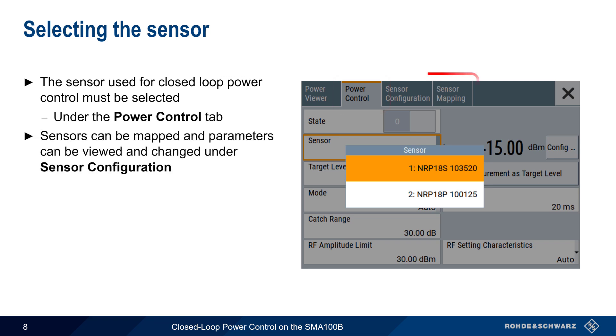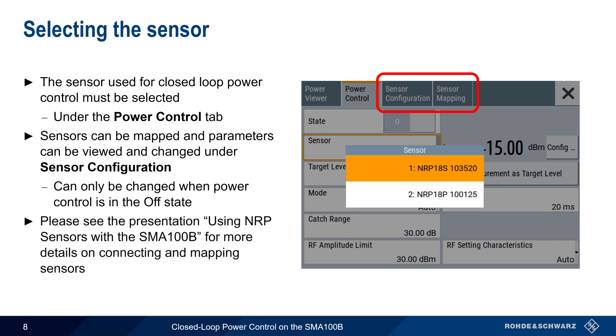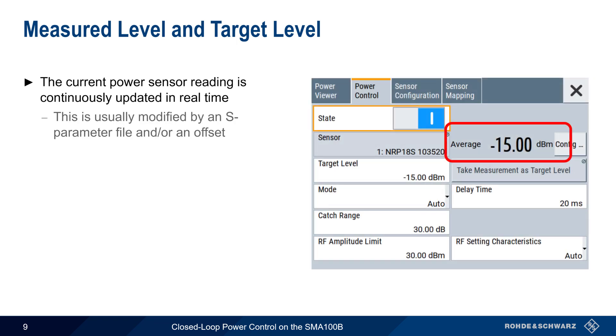Attached sensors can be mapped and parameters can be viewed and changed under the Sensor Configuration and Sensor Mapping tabs. Note that this is only possible when power control is in the off state. In this presentation, we won't go into detail on how to attach and map sensors, so please see the separate presentation, 'Using NRP Sensors with the SMA100B,' if you need more information about this topic. The power sensor reading is continuously updated in real time, although remember that this value is usually modified by an offset or an S-parameter file.